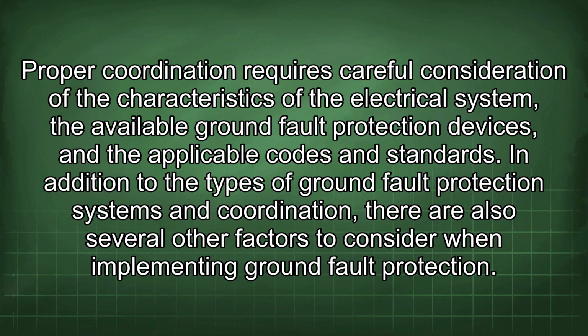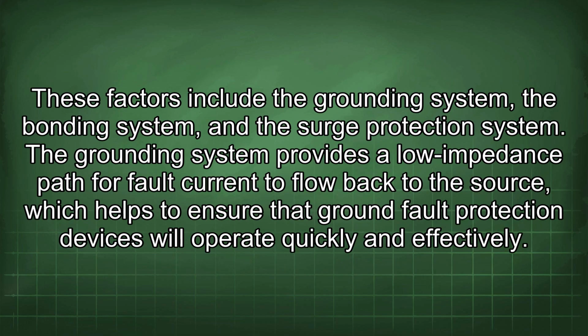In addition to the types of ground fault protection systems and coordination, there are also several other factors to consider when implementing ground fault protection. These factors include the grounding system, the bonding system, and the surge protection system. The grounding system provides a low impedance path for fault current to flow back to the source, which helps to ensure that ground fault protection devices will operate quickly and effectively.